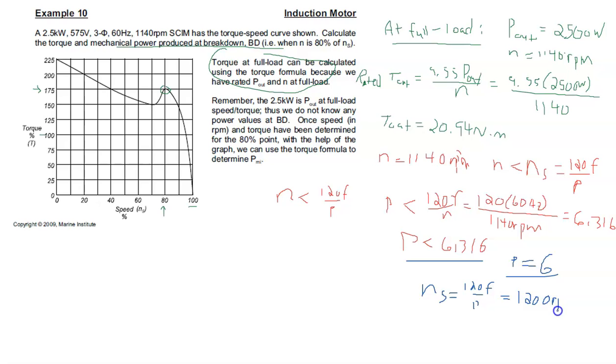So 1200 RPMs. Let's think about how that relates to our graph. If this number is 1200, when we're running at full load right here, does that equate to 1140? Well, sure it does. There's about 5% slip there. 5% of 1200 is exactly 60, and that's our slip speed. So N, 60 below Ns, that makes good sense. We've made the right decision.